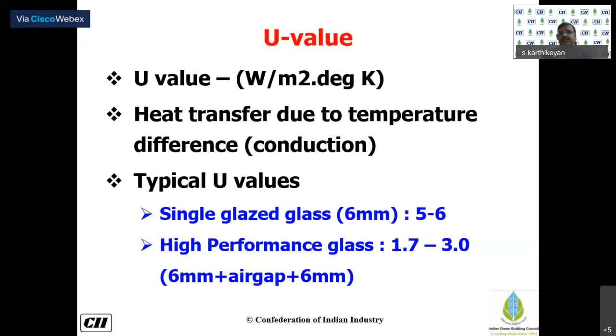On the other hand, high performance glass has a U value of only about 2, typically ranging 1.7 to 3. That means it allows only about 20 watts of energy to come in for the same 10 degree difference. So a single glass allows about 60 watts of energy in, whereas high performance glass allows only 20 watts - it reduces the heat gain to one-third. So obviously I need a high performance glass to reduce the heat gain.